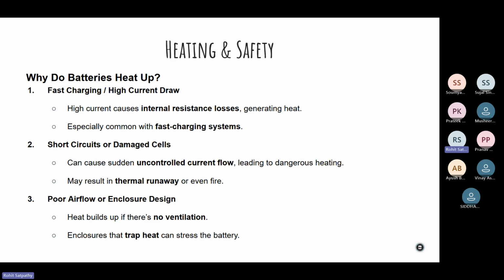The third point: poor airflow and enclosure design. If the heat which should be dissipated is trapped, it will destroy the battery from inside. Simply, you saw LiC6 - if the LiC6 compound has higher energy, what happens? First, the Li bond will break, even though there's no dissociation in electrons. Then the carbon bonds will start to break in the graphite. This results in damage to the cell.